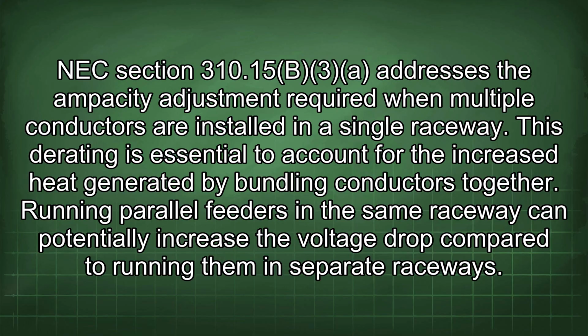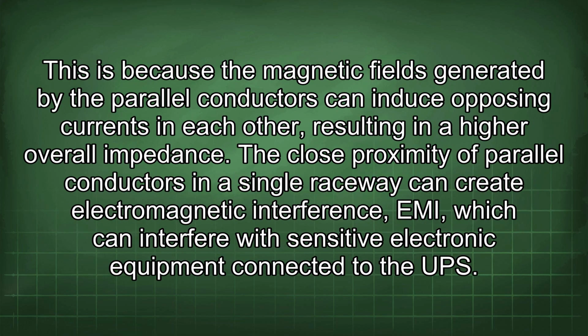Running parallel feeders in the same raceway can potentially increase the voltage drop compared to running them in separate raceways. This is because the magnetic fields generated by the parallel conductors can induce opposing currents in each other, resulting in a higher overall impedance. The close proximity of parallel conductors in a single raceway can create electromagnetic interference, EMI, which can interfere with sensitive electronic equipment connected to the UPS.